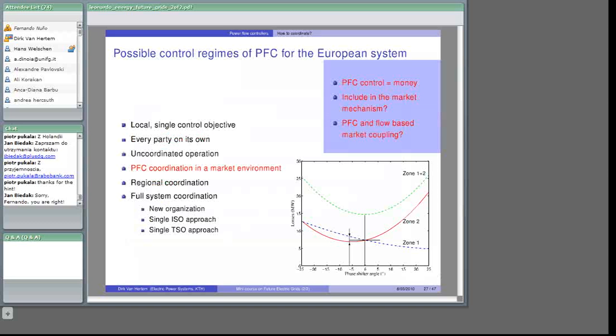There is a difference in losses, meaning a difference in system operating cost between zone 1 and zone 2. Maybe zone 1 is willing to pay zone 2 to move its phase shifter angle towards 0, providing compensation for the extra losses for zone 2, so there might be something in it for both of them.